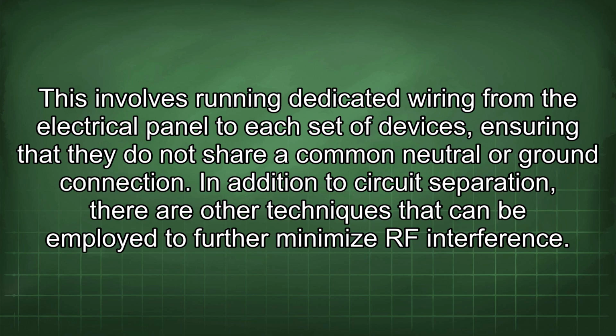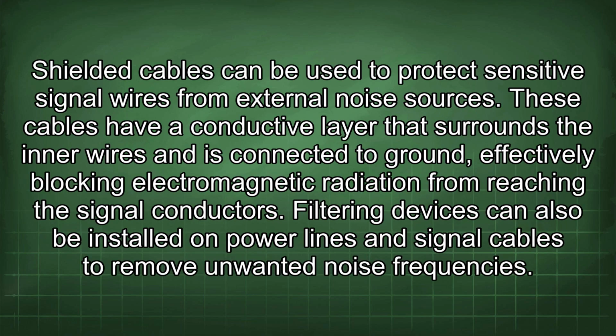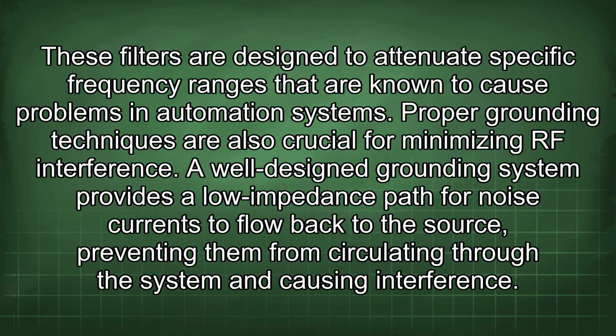In addition to circuit separation, there are other techniques that can be employed to further minimize RF interference. Shielded cables can be used to protect sensitive signal wires from external noise sources. These cables have a conductive layer that surrounds the inner wires and is connected to ground, effectively blocking electromagnetic radiation from reaching the signal conductors. Filtering devices can also be installed on power lines and signal cables to remove unwanted noise frequencies. These filters are designed to attenuate specific frequency ranges that are known to cause problems in automation systems.